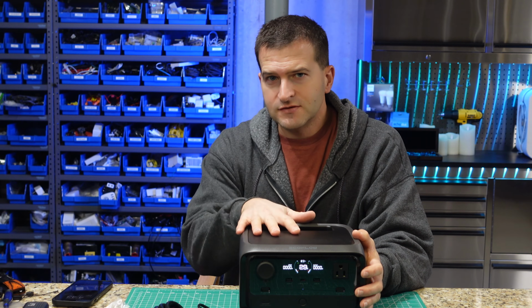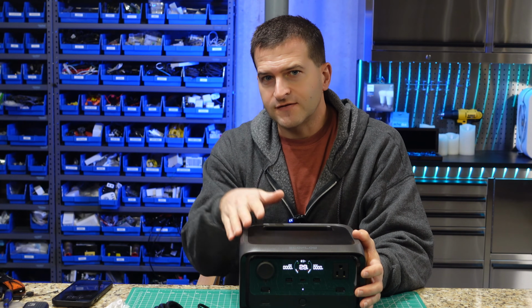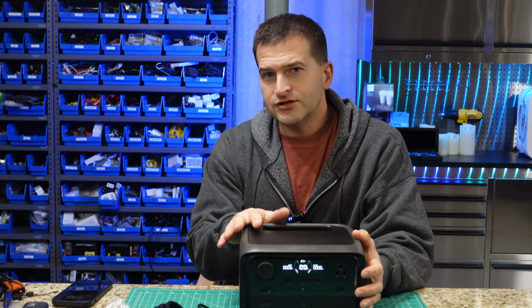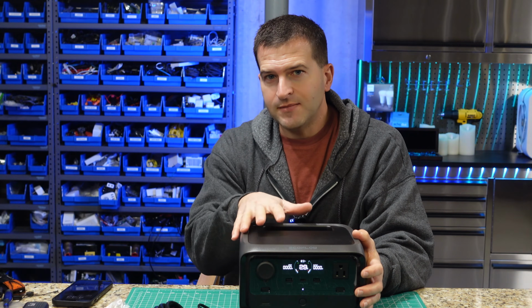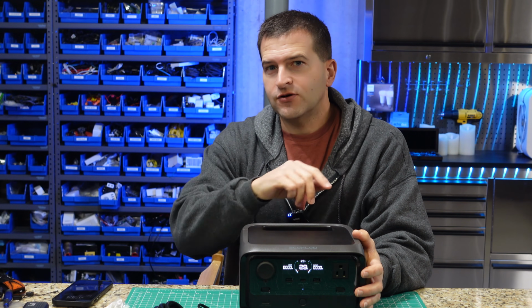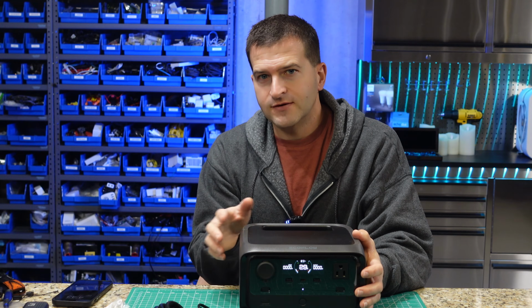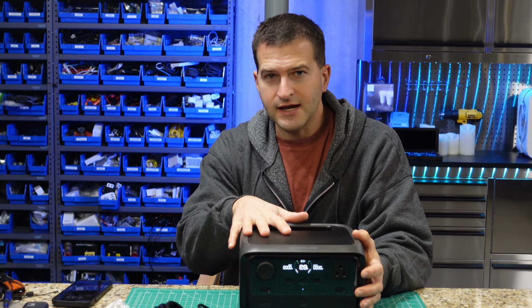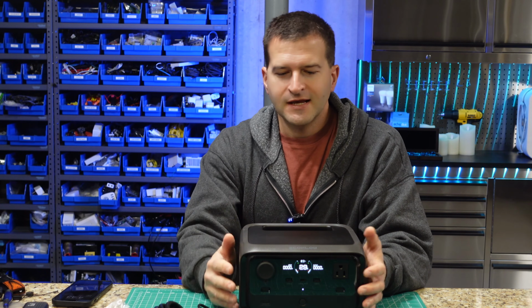So you could have two side by side, do your update on the first one, then the second one. That actually isn't a terrible way to go, because when the battery dies in the first one, it'll automatically fail over to the second one if you have a PDU that's only drawing from input A and switches over to input B. So that is an option.